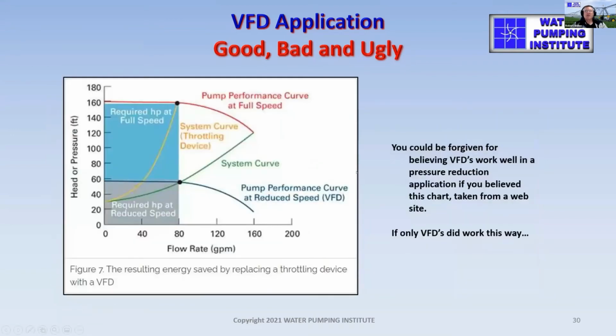I just want to show you, this is something that I saw on the internet. Here's somebody's portrayal of a pump curve at full speed, and here's the pump curve at a reduced speed. Now, this doesn't show any movement down and to the left. So that pump curve on a VFD shows that you can pull the same flow just at a reduced head. That is totally wrong. It is misinformation.